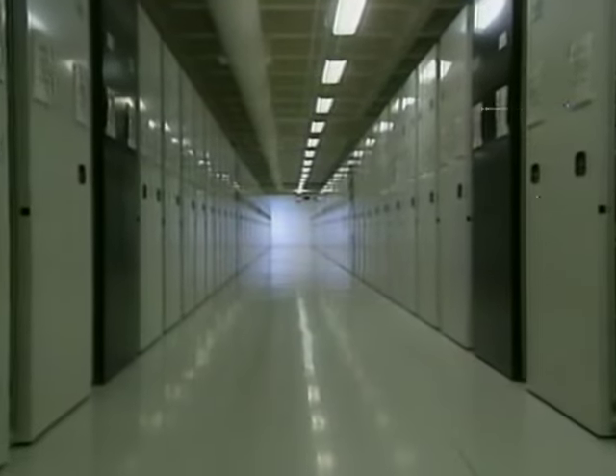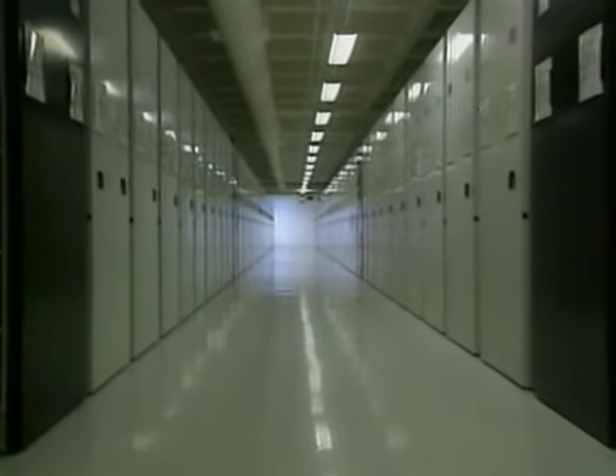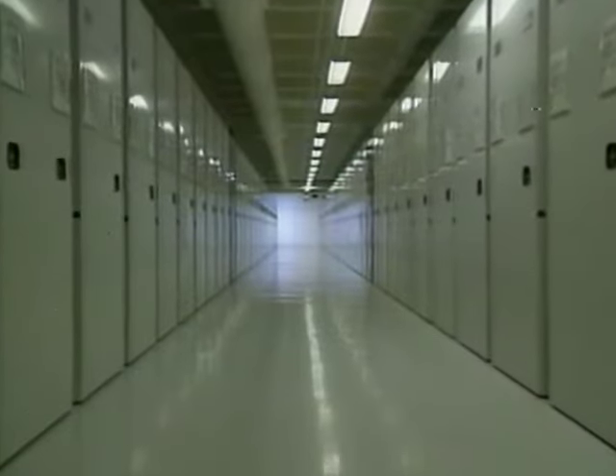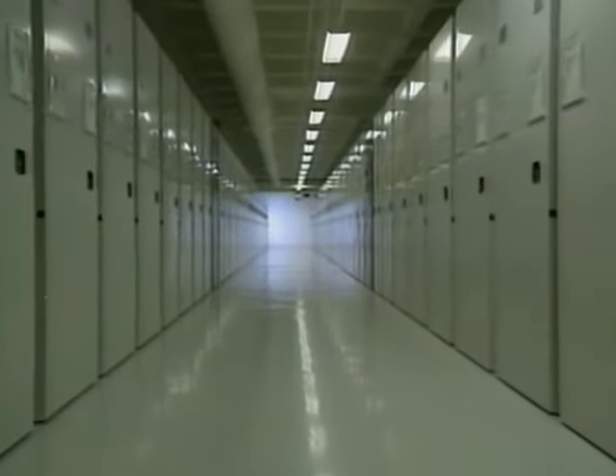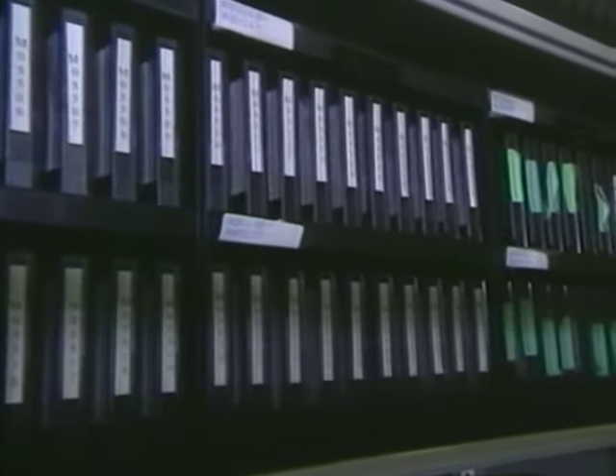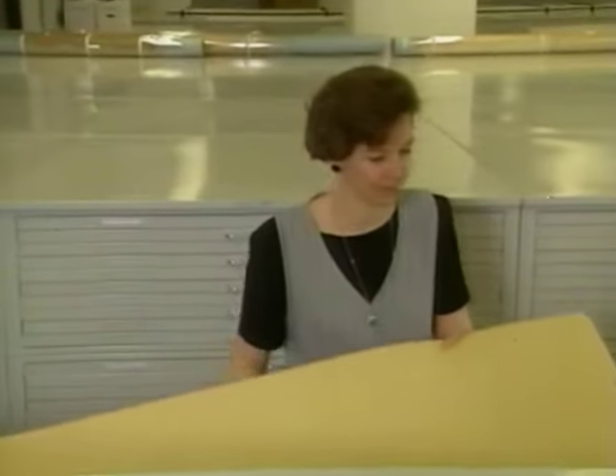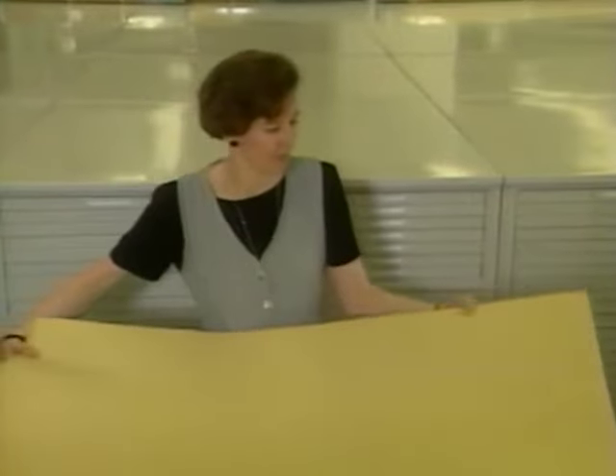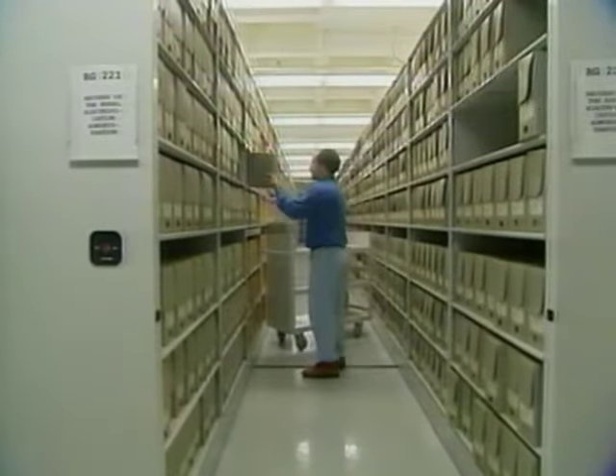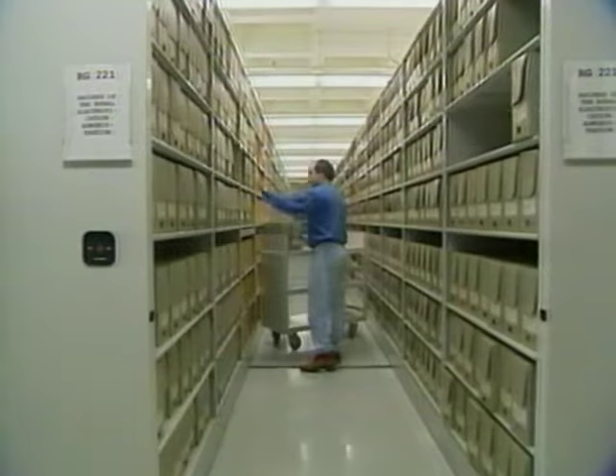What we achieved here at Archives 2 is significant because of the mammoth size of the undertaking here in the building. The space devoted to archival storage represents roughly half the total size of this building. And when you consider that the air quality in half the size of this building is comparable to what normally is achieved in a 20 to 30,000 square foot computer chip facility, I believe that's what makes the difference between what was achieved here at Archives 2 versus conventional technology.